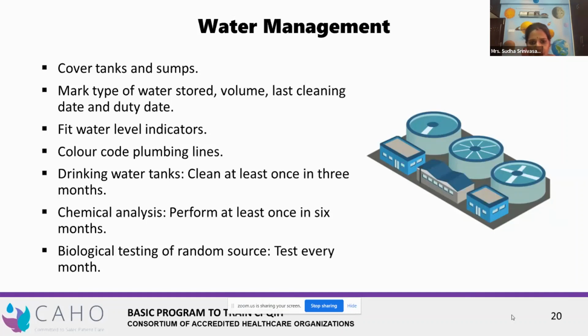Many times when we look at the water tanks, often they are not accessible. You'll find overhead tanks above some building, and when asked, they say they clean it every month, but when we actually go and see, there is no ladder or any access. So how do they actually climb? We can't put the people who clean at risk, so adequate safety measures have to be ensured, and they should be taught how to actually clean the water tanks.